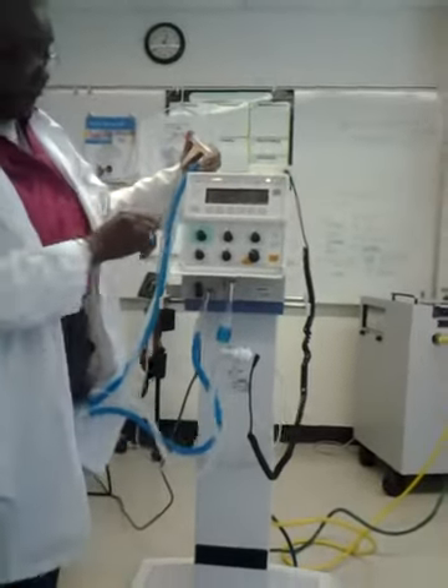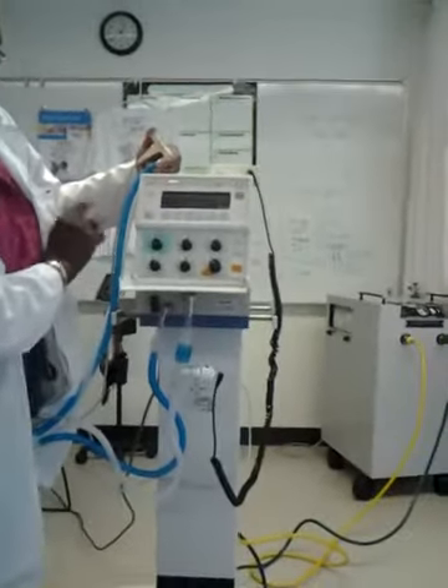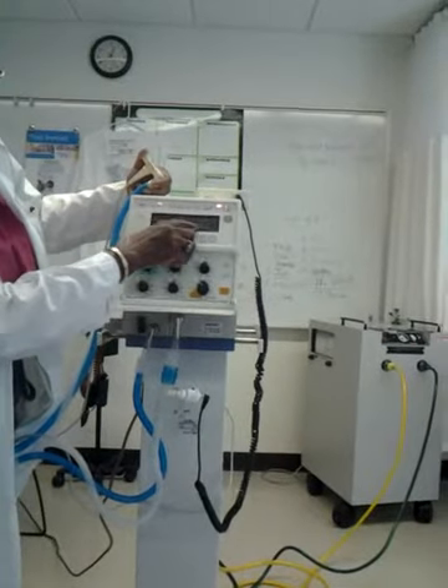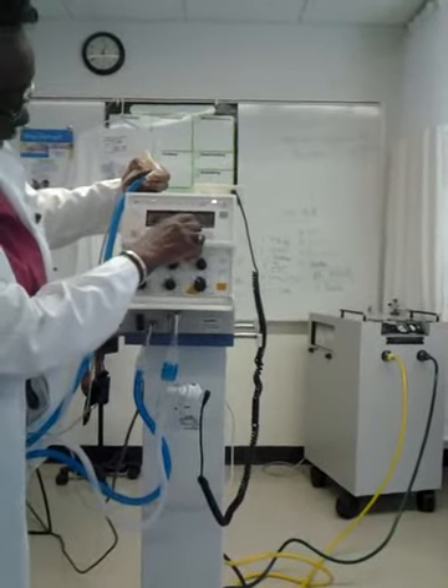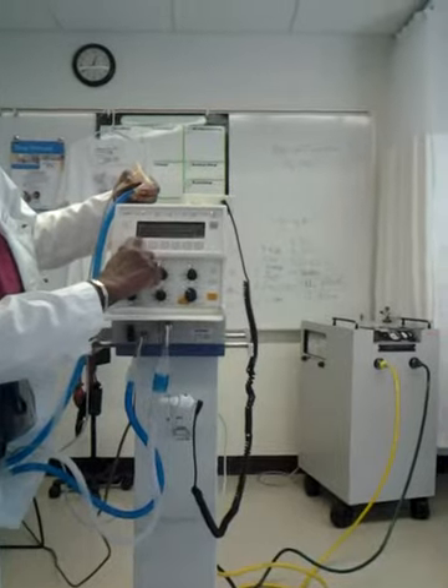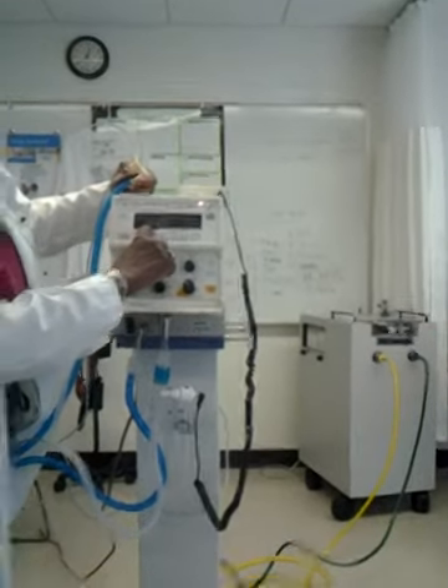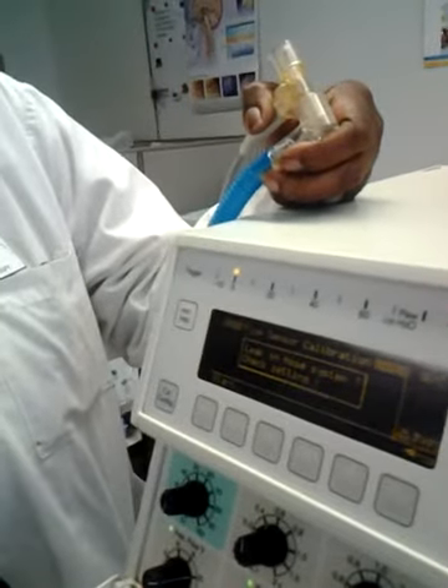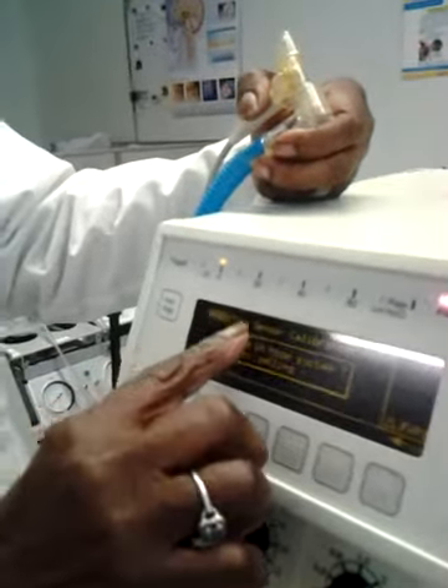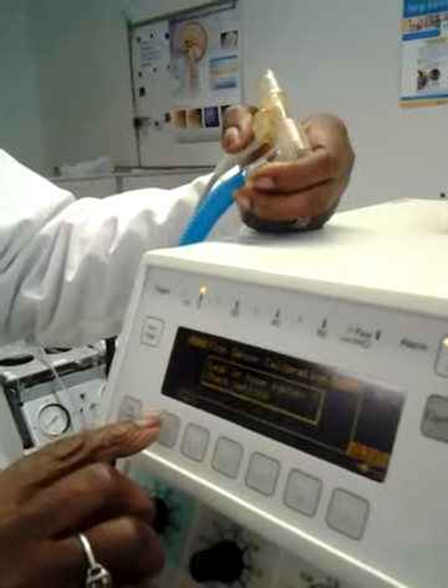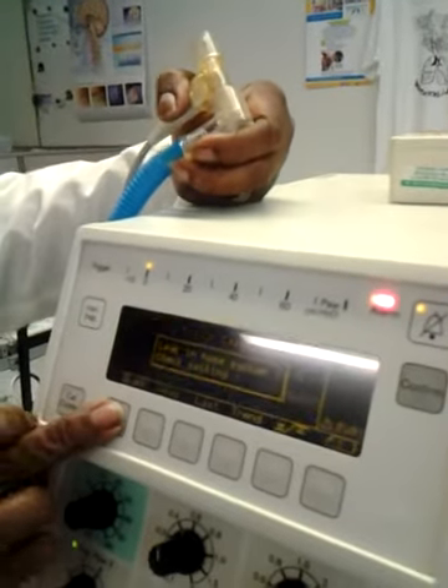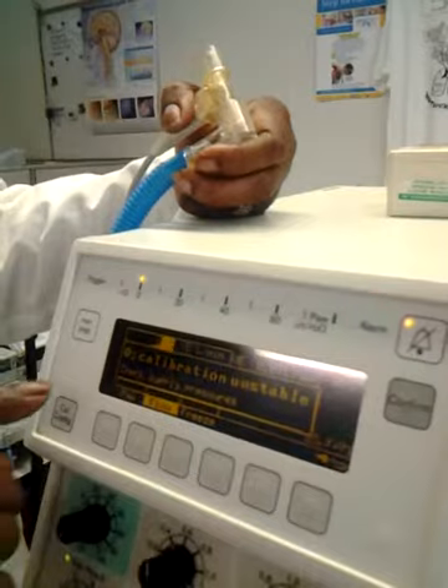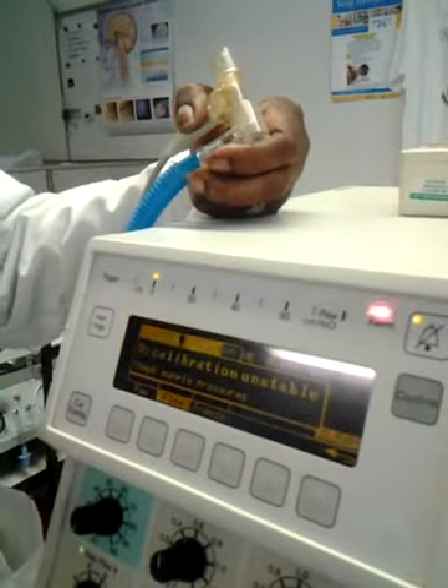Those are the... You have to go into Cal configuration. It says tube obstructed. It goes across up here, calibration, and at the bottom here it says calibrate flow, or your O2 sensor. So if I want to calibrate the flow sensor, I hit the button underneath there, and now it's calibrating my flow sensor. So you don't have to include anything? It tells you what to do. Okay, flow sensor calibration, and then it says start. And now it wants to know if I want to calibrate the O2 sensor.